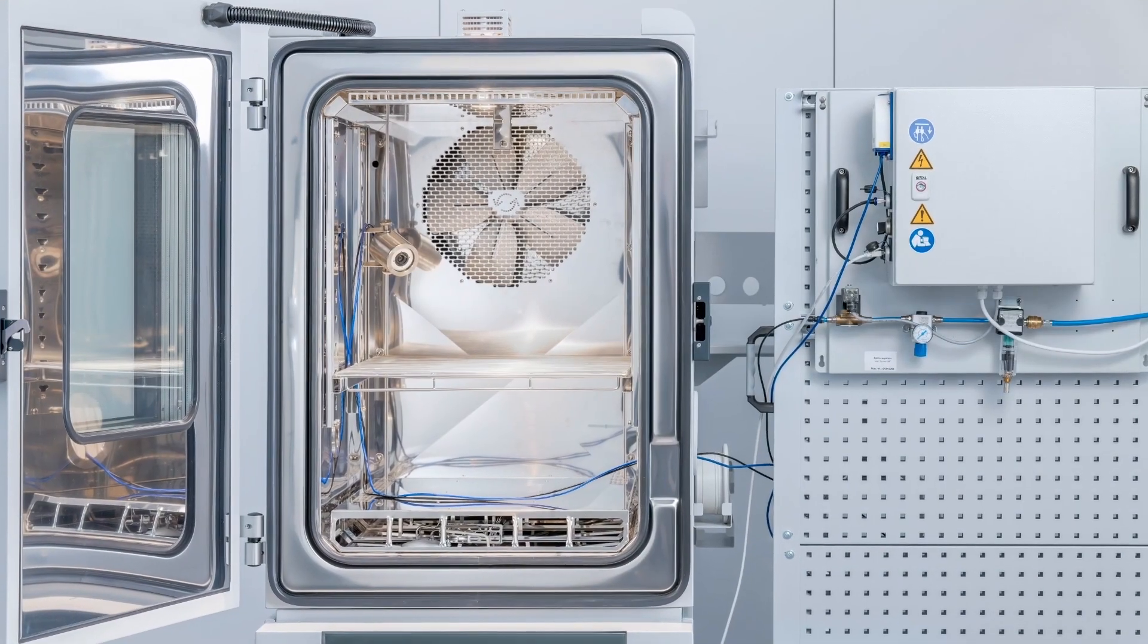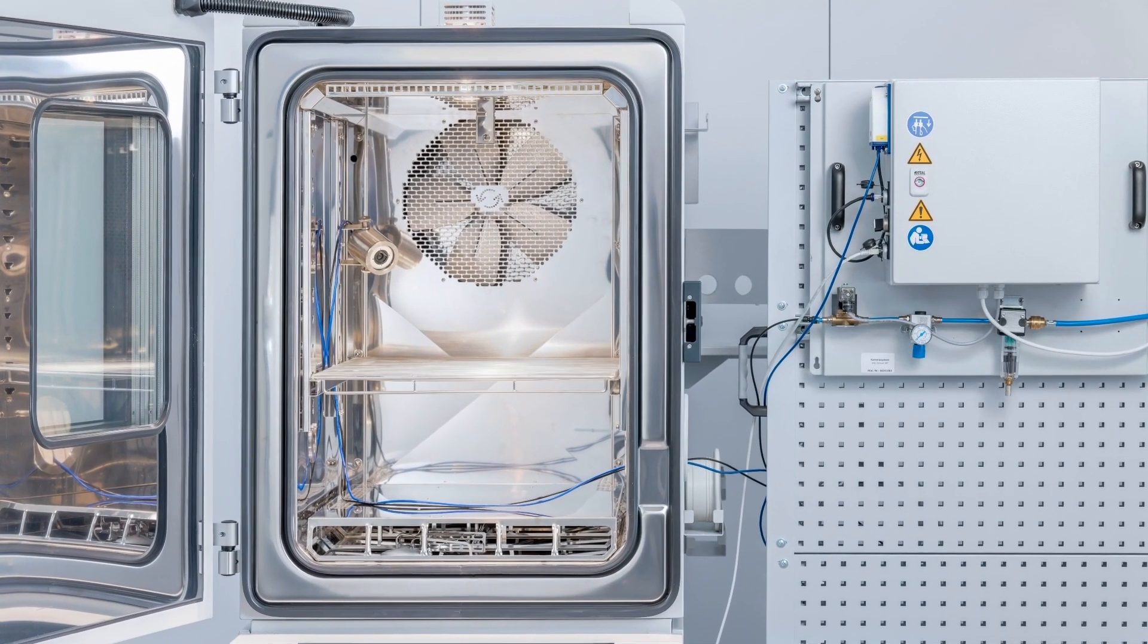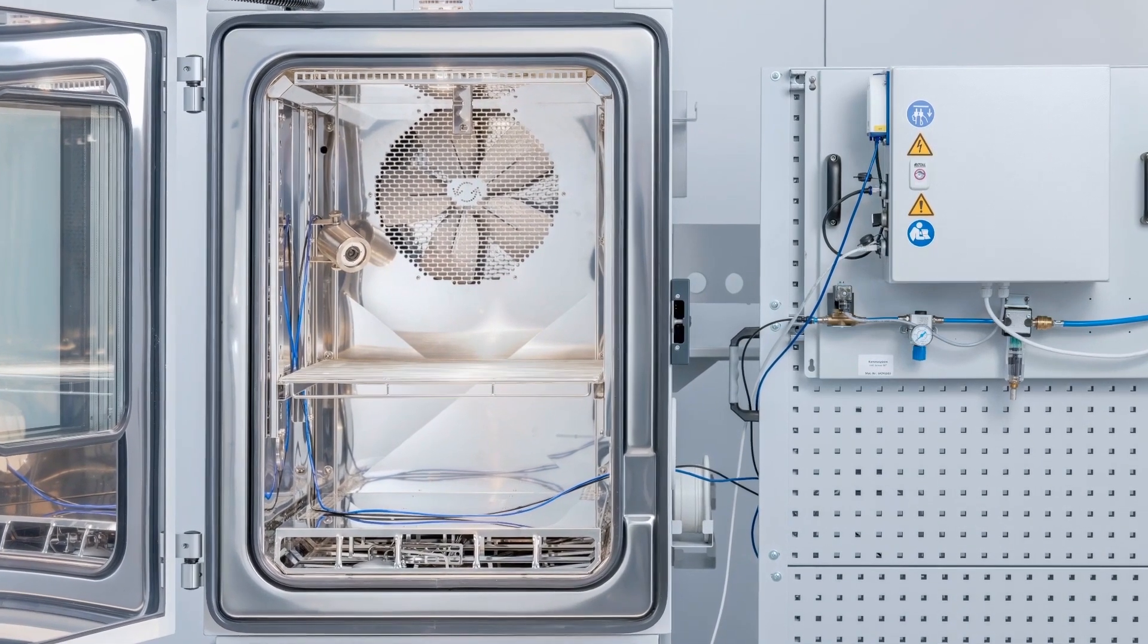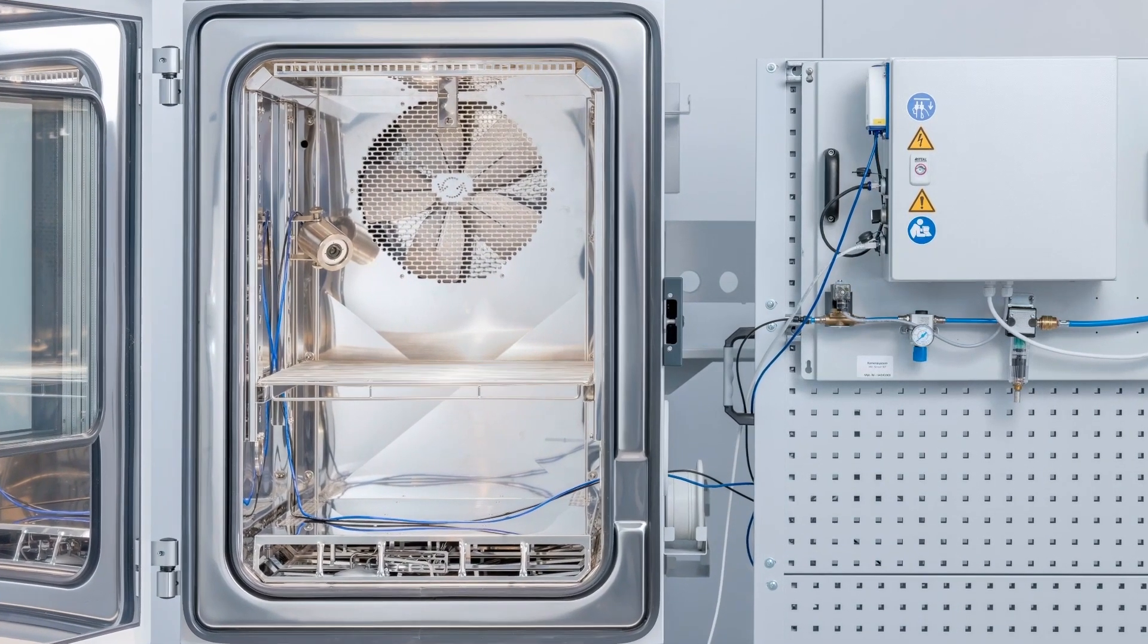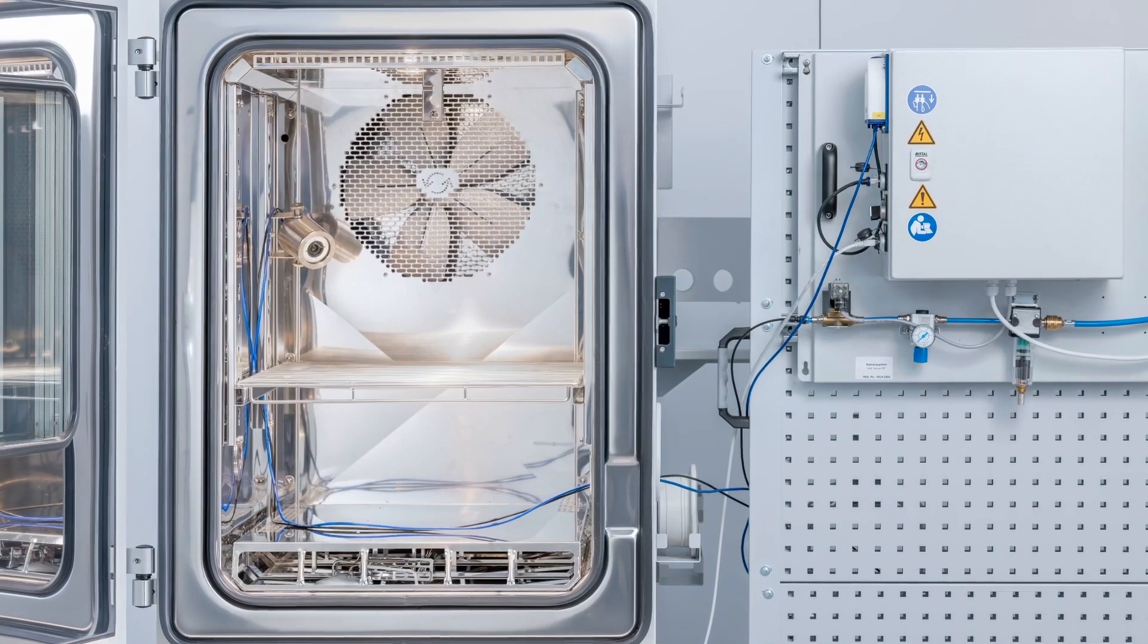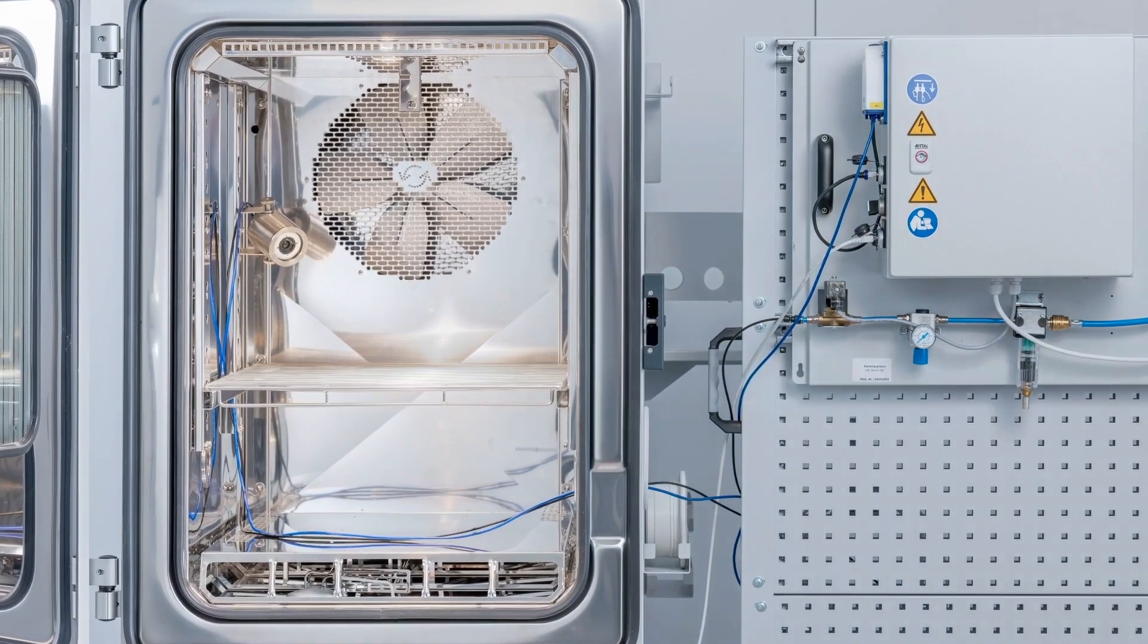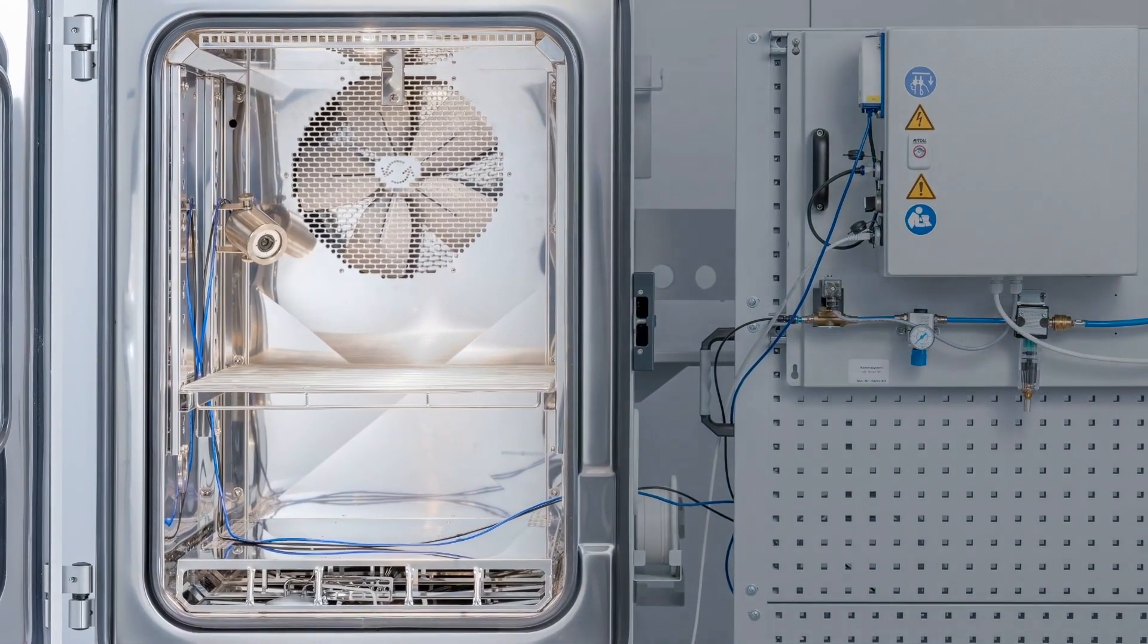The Sympati software module Timelapse together with a compressed air purged camera system is the Weiss Technik solution for image recording in climate test chambers from minus 40 to plus 80 degrees Celsius at a relative humidity of 10 to 95 percent.